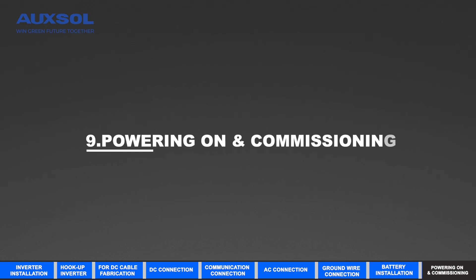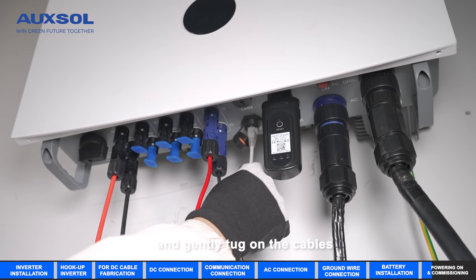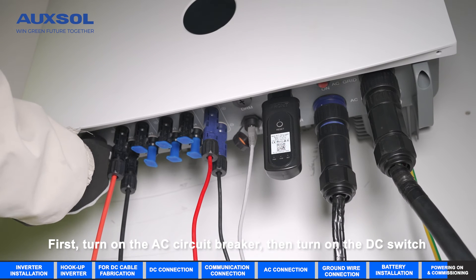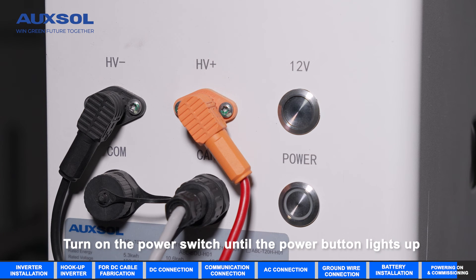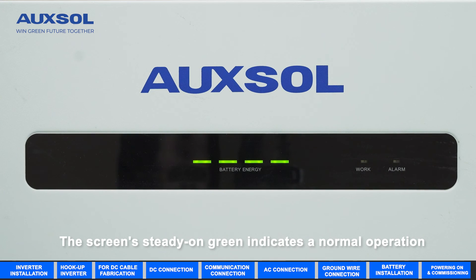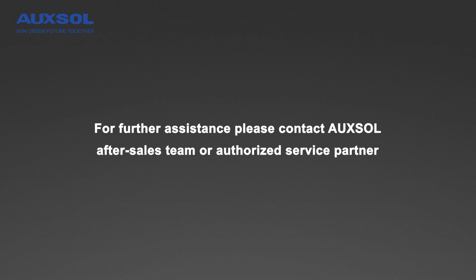Powering on and commissioning: please double-check that all connections are correctly made and gently tug on the cables to ensure they are tightly linked. First, turn on the AC circuit breaker, then turn on the DC switch. Turn on the power switch until the power button lights up. Press and hold the power button for 5 seconds to activate the battery. A green screen indicates normal operation. For further assistance, please contact the AUXSOL after-sales team or an authorized service partner.